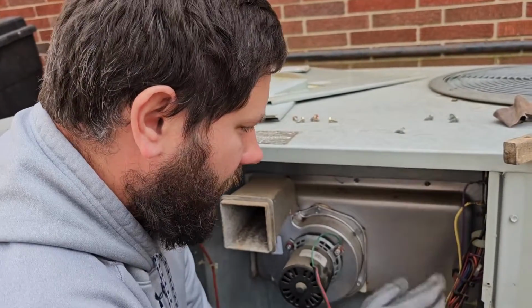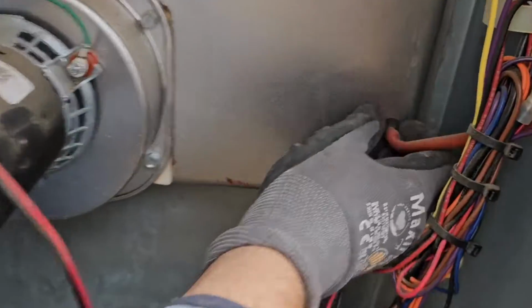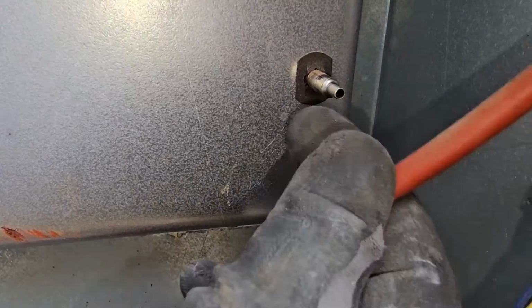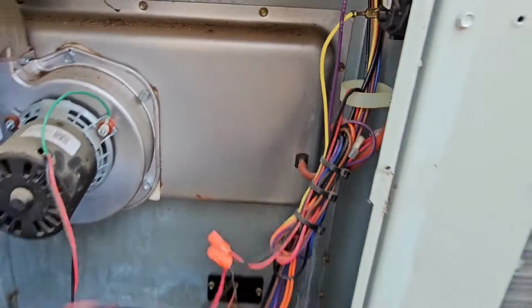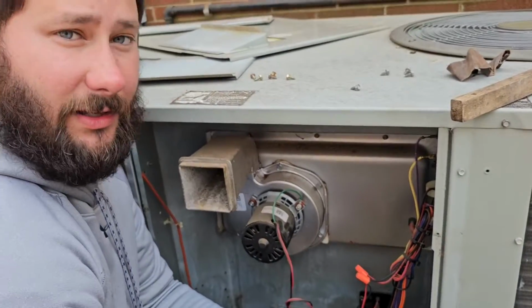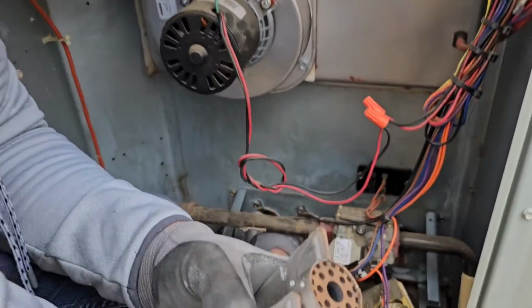If you see, take the inducer motor off. If you see the inducer motor blades are falling apart or they're rusted, go ahead and get the customer a price. I'd rather go ahead and take care of it. That way they're not out of heat on the coldest day of the winter. Also, this tube right here for the pressure switch, take that off. Take a look inside the hole. Stick something in there. Make sure you clean it out, because that can become stopped up, and that's an easy service call. And you'll get 20 of those beginning of winter.